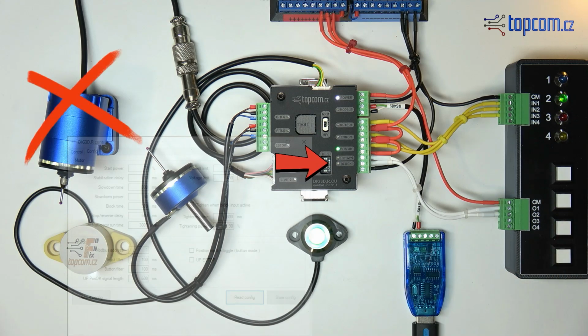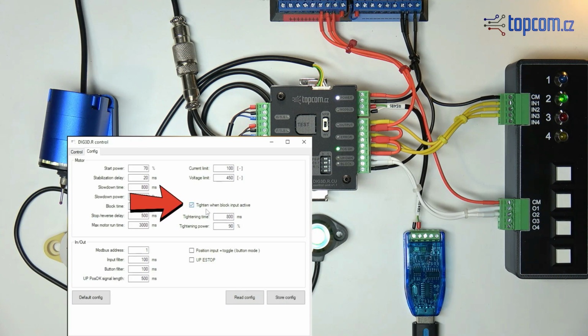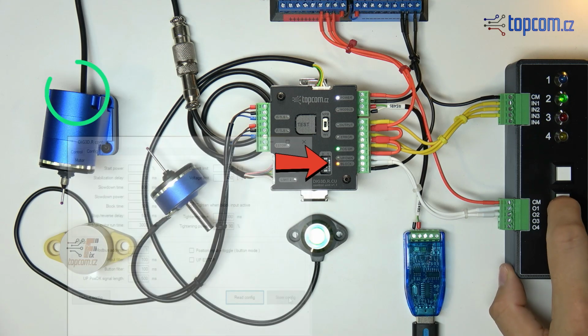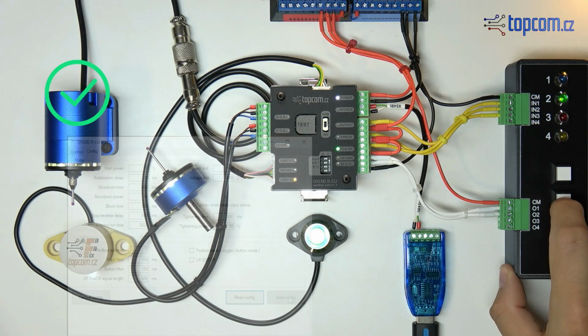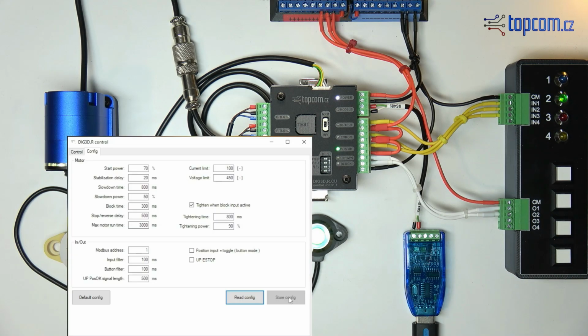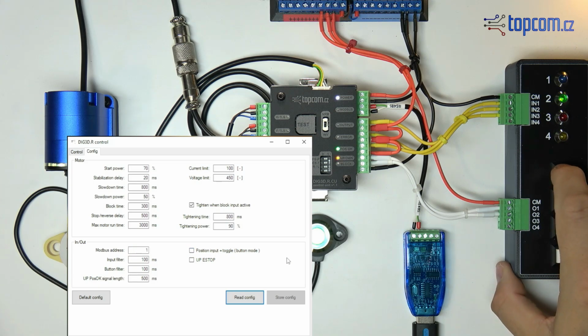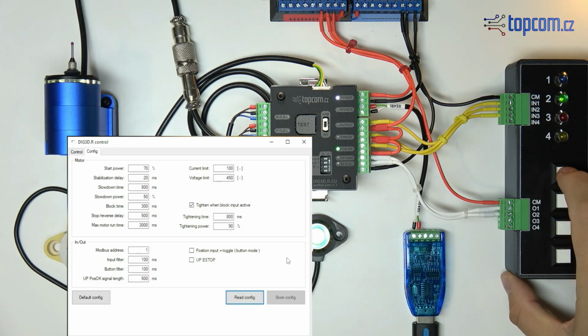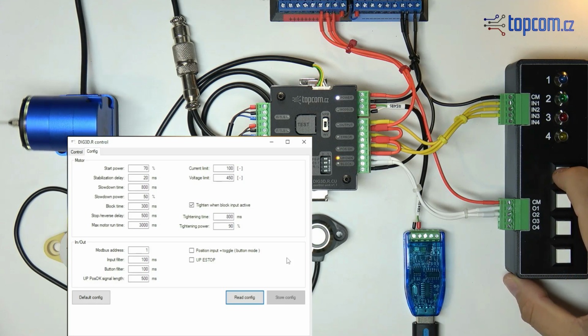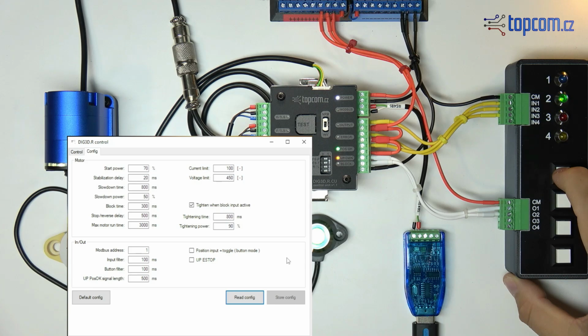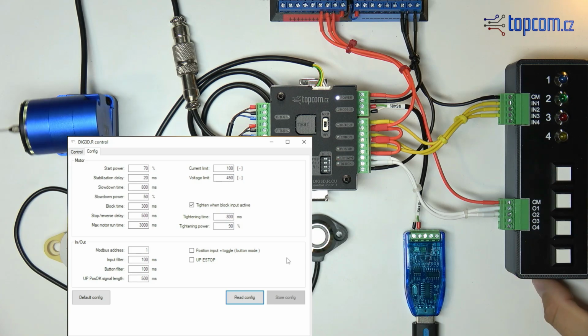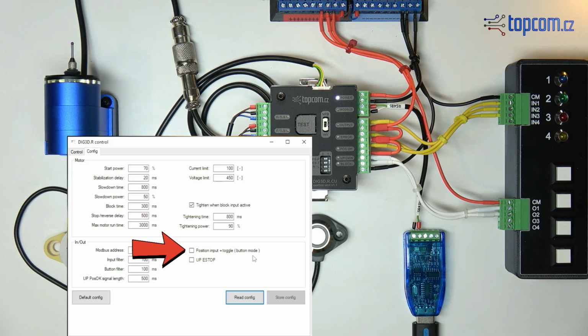However, if this function is enabled, the probe is always retightened with a defined force for a specified duration whenever the block signal is activated. Another parameter configures the function of the up-down input. By default, this input is intended for automatic control. An inactive signal means the probe remains in the home position, while an active signal rotates it into the working position. You can also connect an additional button for manual control to this input.